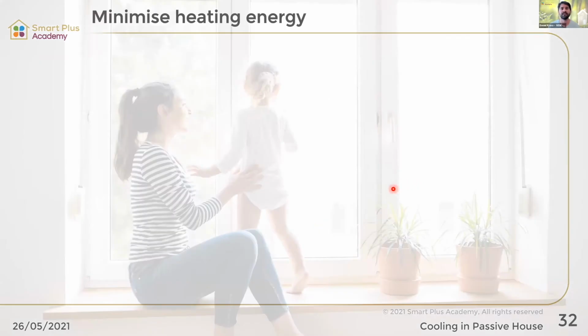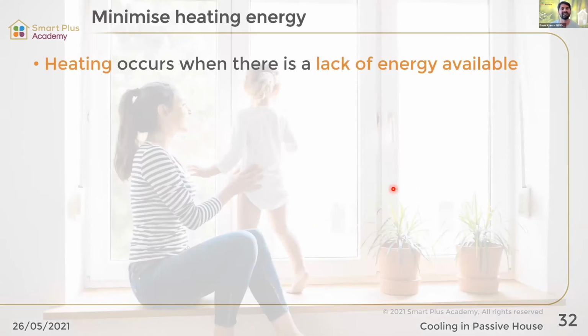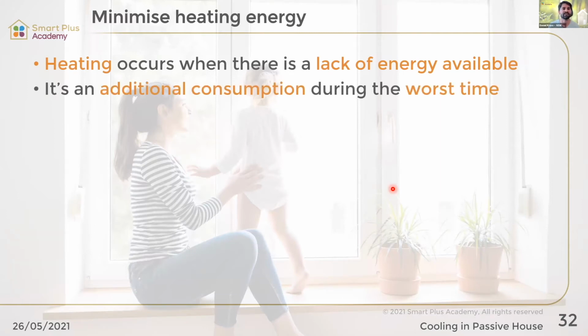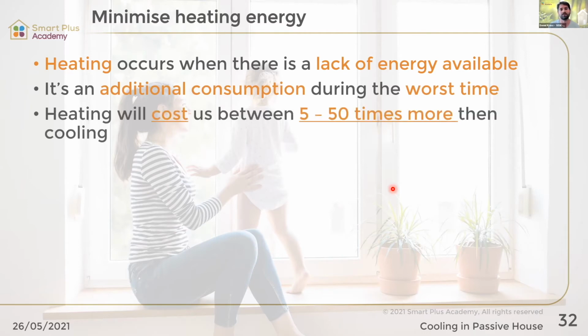So minimizing heating energy: heating occurs when there is a lack of energy available, the sun is not shining, it's additional consumption during the worst time. The heating cost will be between 5 to 50 times more than the cooling cost, depending on where you are in the world. So even in climates like Sydney, we still design for the cold season, because the cold season will cost more than the hot season. The hot season, from an operational point of view, costs us nothing. The investment cost upfront is probably about 2 cents per kilowatt hour.